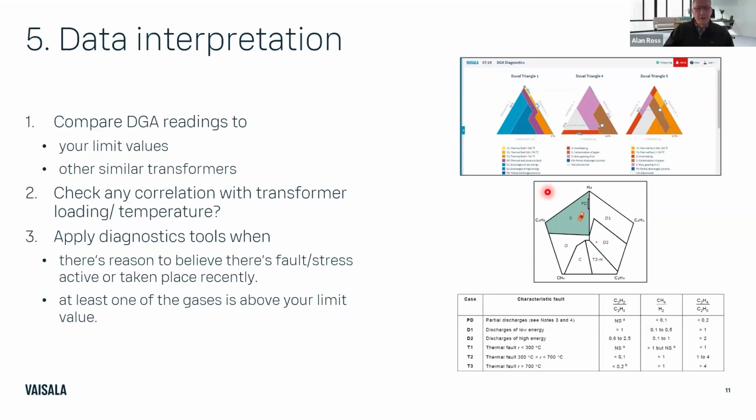Of course, it's not a fault. Some gases are formed naturally in the transformer. So I used to say that I only use these tools if there is a reason to believe that there is a fault or thermal stress active.